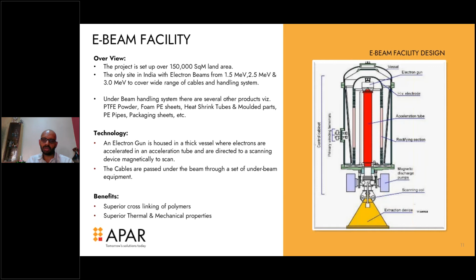What happens is an electron gun, which you can see here, with the acceleration tube here. This is the electron gun. The gun shoots out the electrons into the acceleration tube highlighted in red. They're accelerated, and then there is a scanning device through which the cable passes continuously via the extraction, which gives it cross-linked properties as well. So like I said, again, it offers superior linking of the polymers and thermal and mechanical properties.